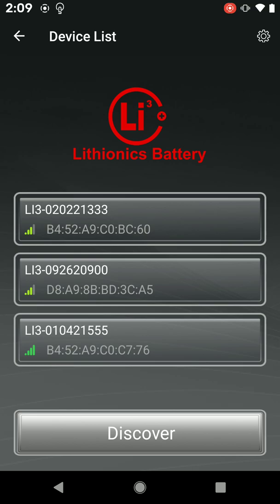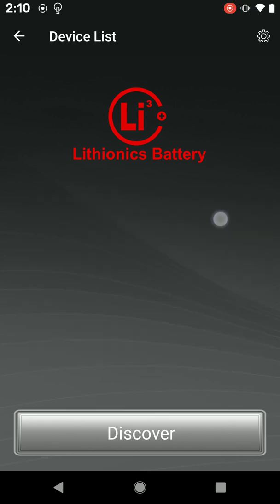All batteries are shipped from the Lithionics factory with default battery ID equal 1 and default CAN SA equal 70. So for the first battery, you don't have to change anything. For battery 2, you have to increment those parameters by 1. On battery 3, increment by 2, and so forth. Here's how it's done using the Bluetooth app.